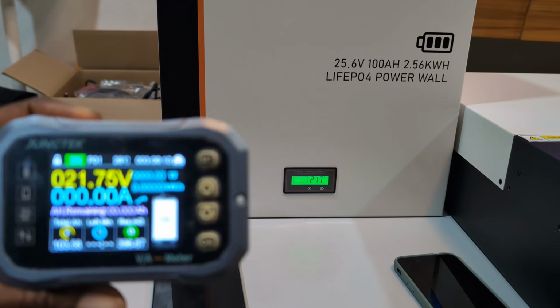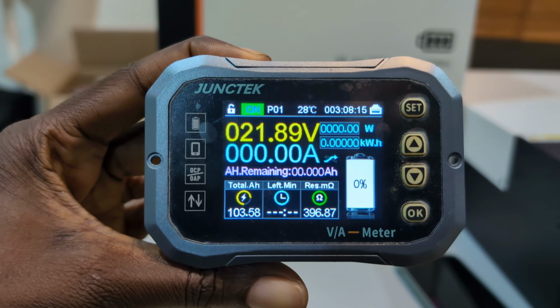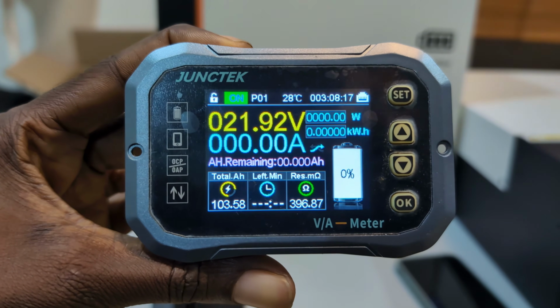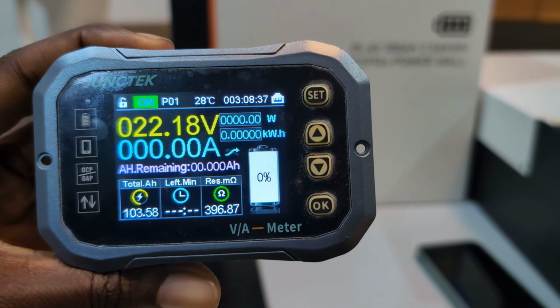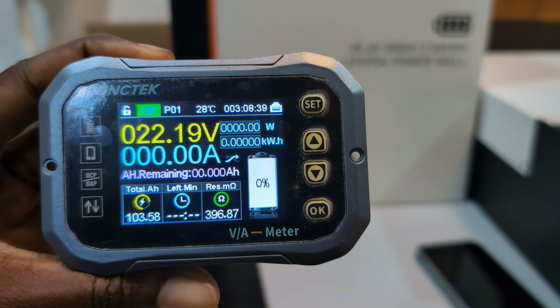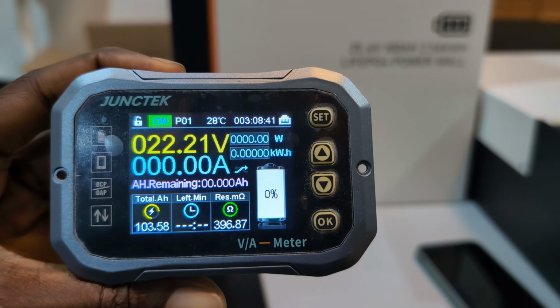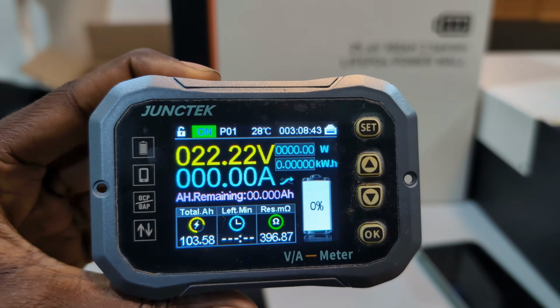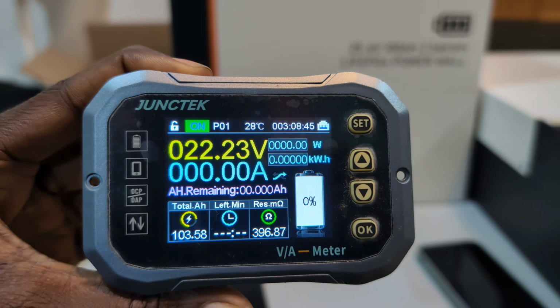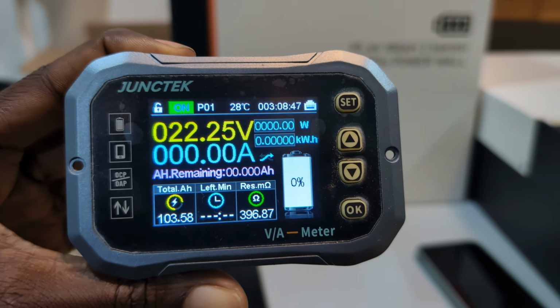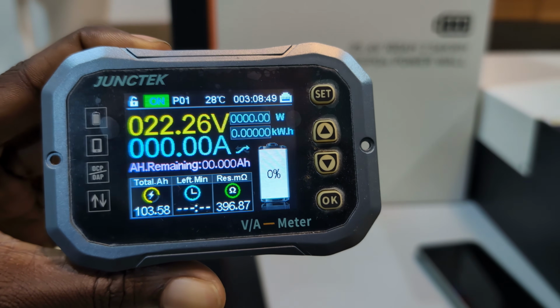So you can see the voltage on the battery bounced up. The inverter shut down before the battery did. We were able to reach 20.8 and the BMS did not shut down, and we pulled 103.58 amp hours. Thank you.